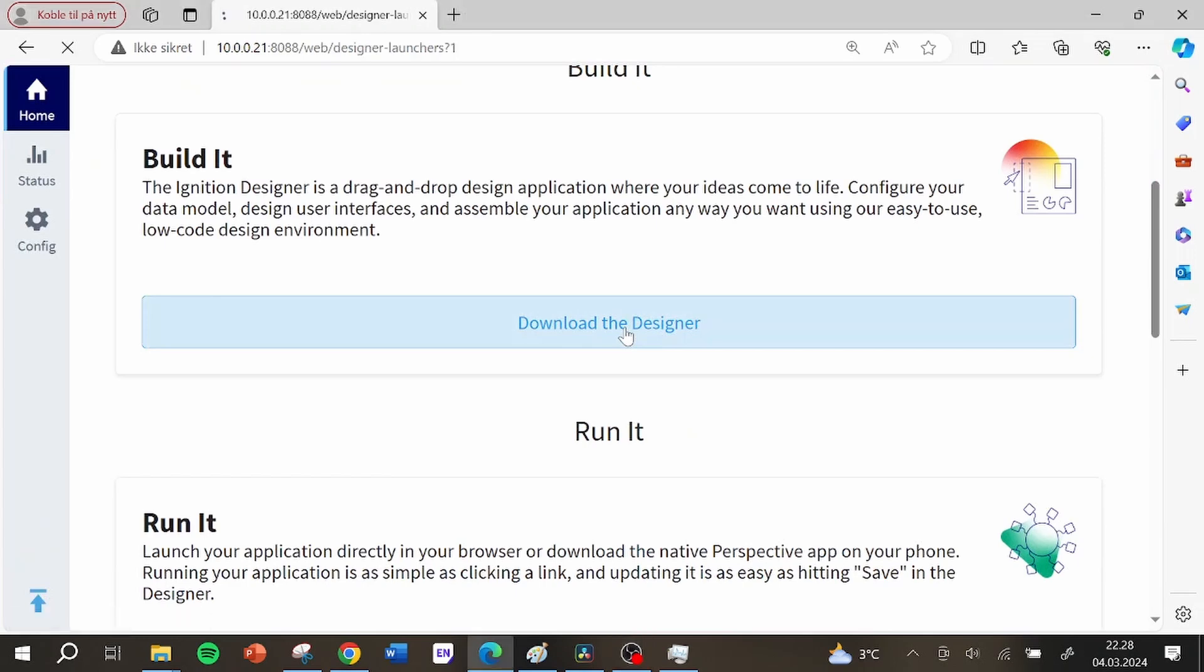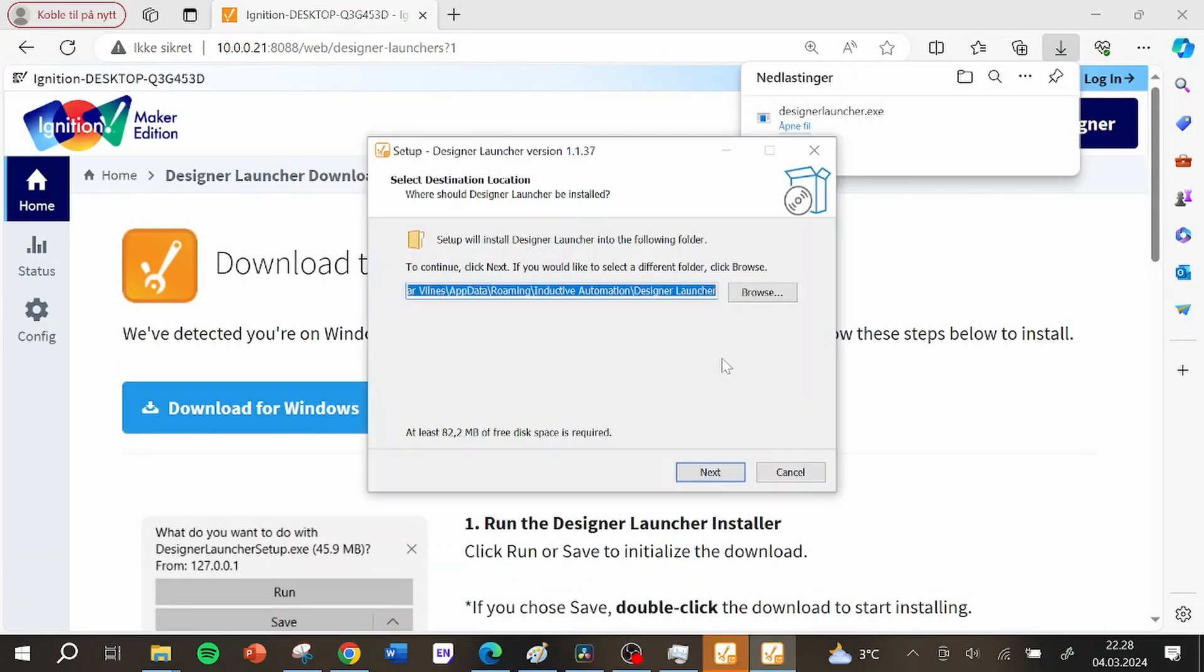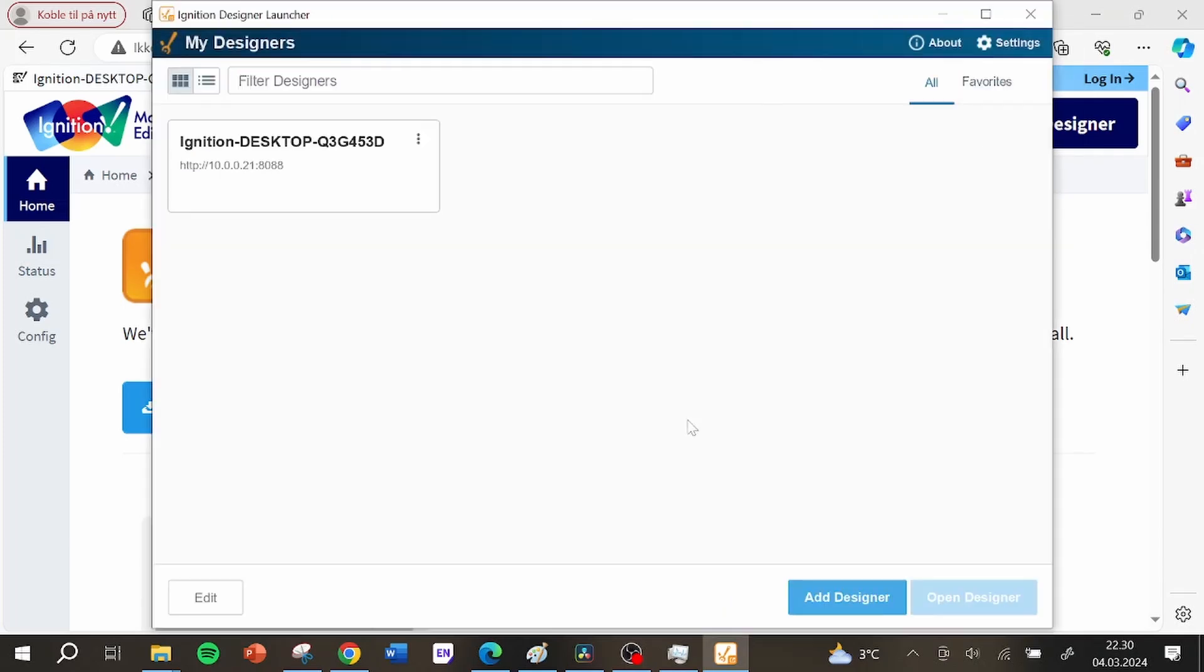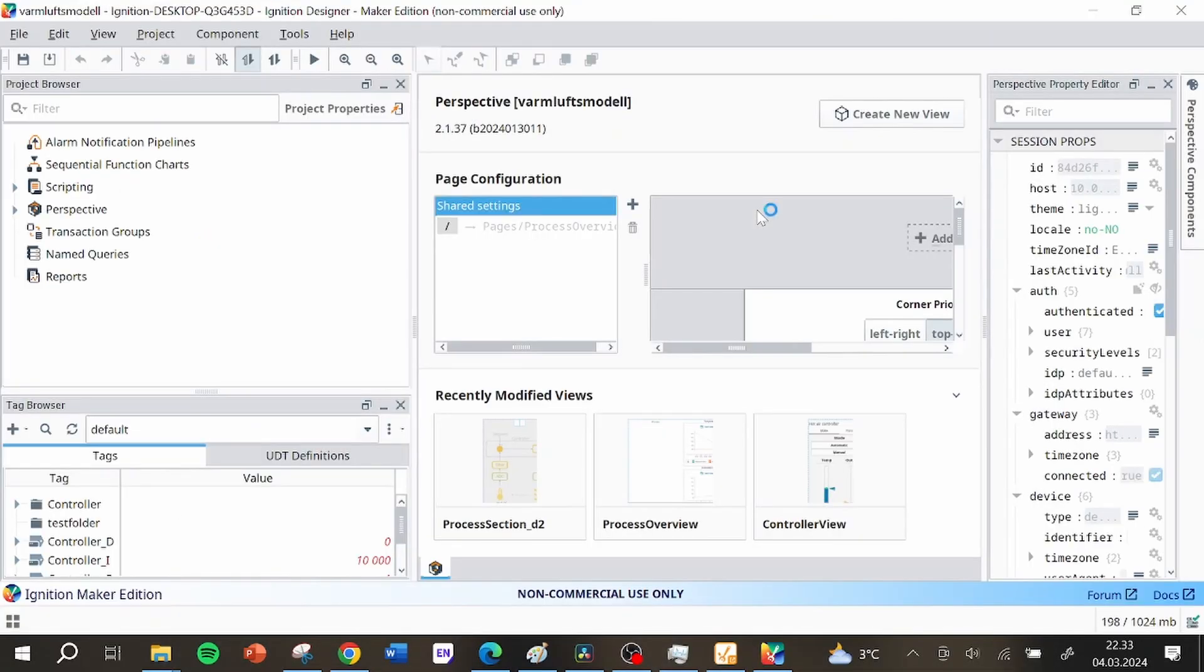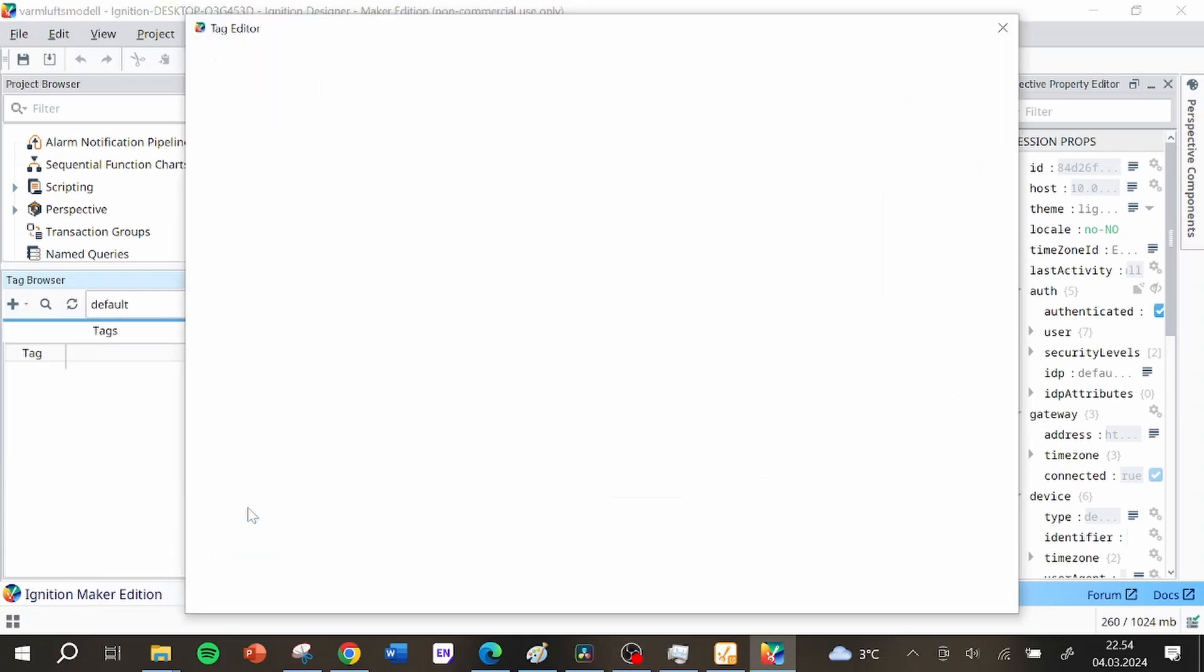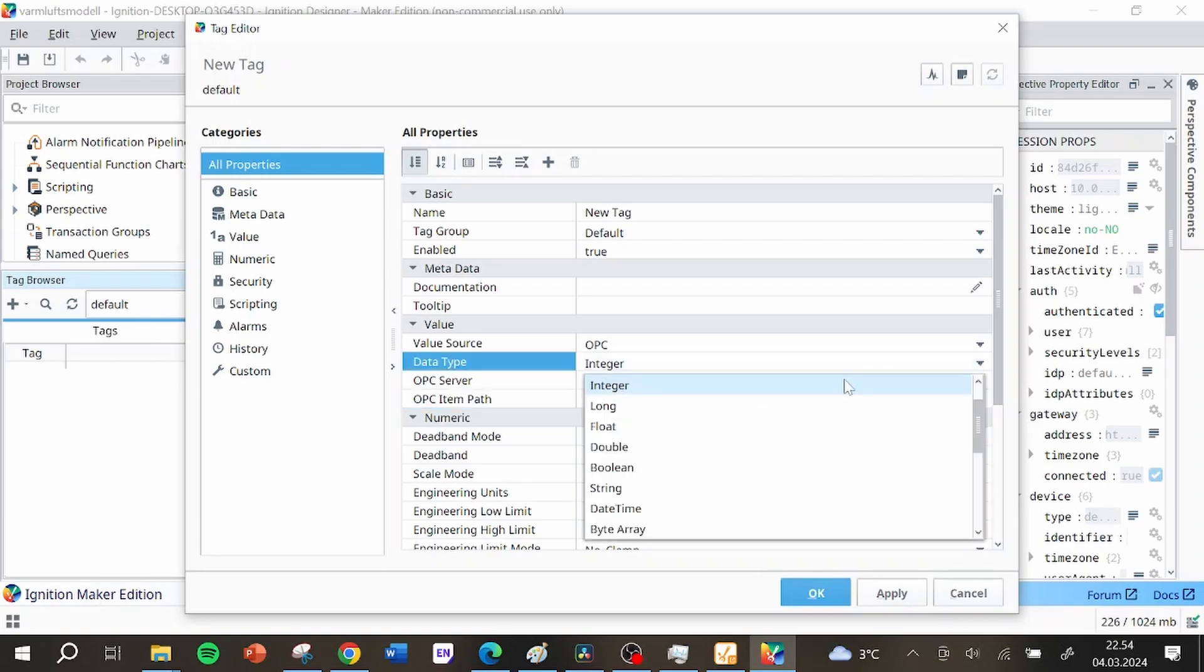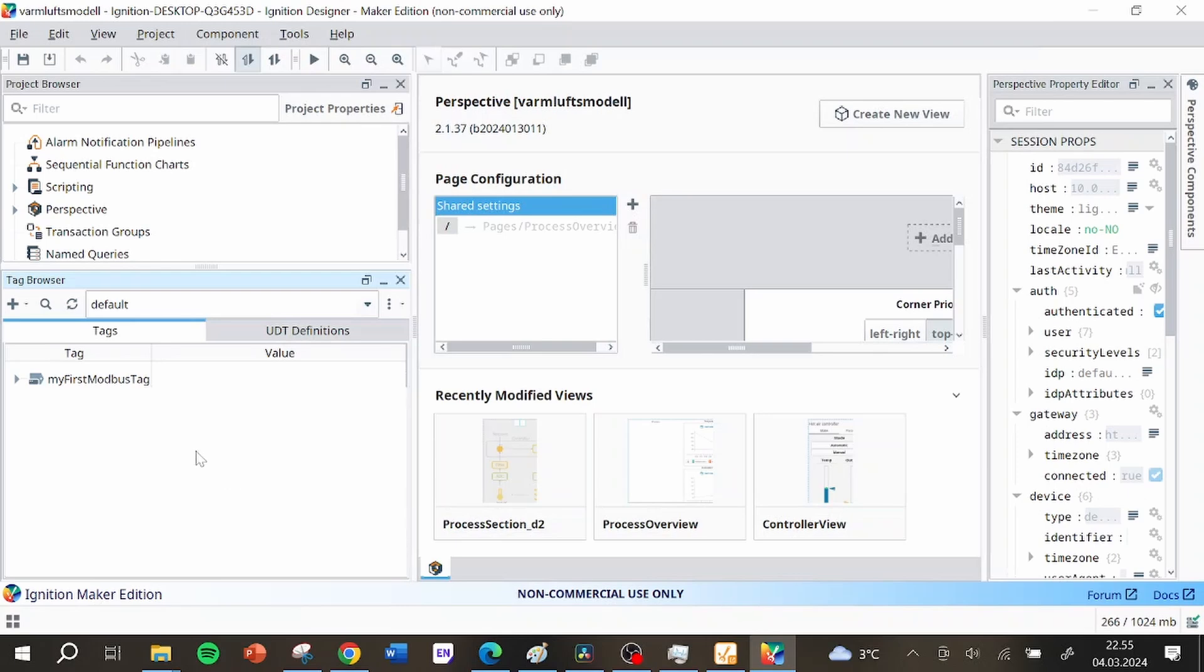From the web interface I then downloaded the ignition designer tool which I downloaded, installed and connected it back to the ignition gateway. I could then log in, choose or create a new project and get the designer up and running. To see Modbus values in the designer I had to add an OPC tag and in the OPC item path I had to add the device name of the Modbus device and hrf0 to get the first floating point number. When saving this I got a new tag in my tag browser and it was receiving the correct value.